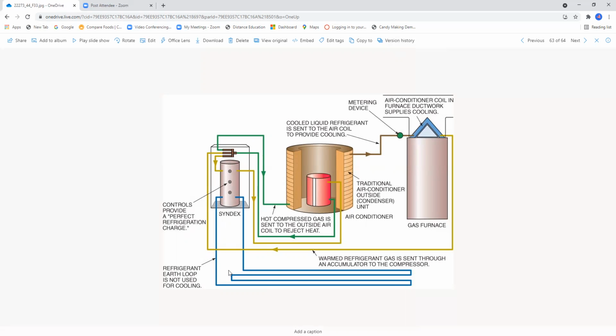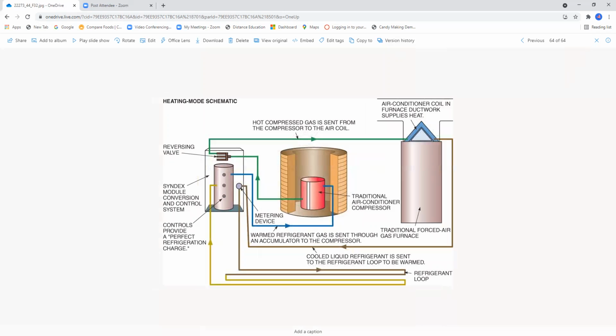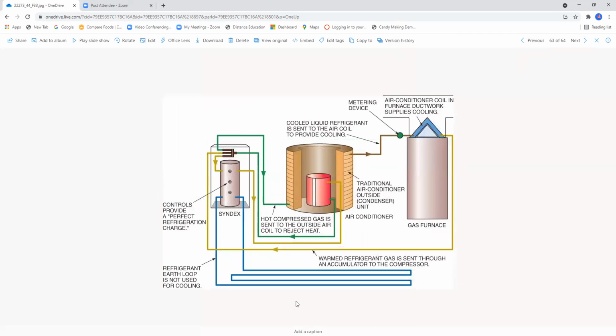The refrigerant earth ground loop is not used for cooling in this application. Now in this application, cooled liquid refrigerant is sent to the refrigerant loop to be warmed. So in this case, we are using the ground loop. In the previous slide, we were not. And basically, the cool liquid refrigerant sent to the air coil will absorb heat in the evaporator coil from the return air, to cool the house down. Hot compressed gas is sent to the outside air coil to reject the heat.